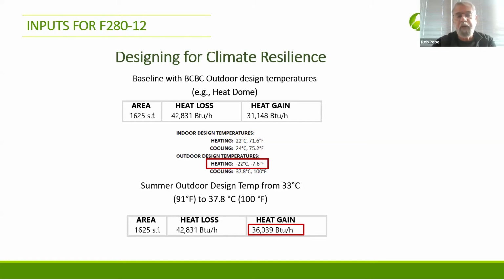And that's what I mean when I say designing for climate resilience. You've got to be careful. Design to the climatic data for the summer in that area is fine, but then you're going to manage client expectations, because the chances of it going above that temperature for a sustained period of time is high, right? So we like to design to a higher temperature.